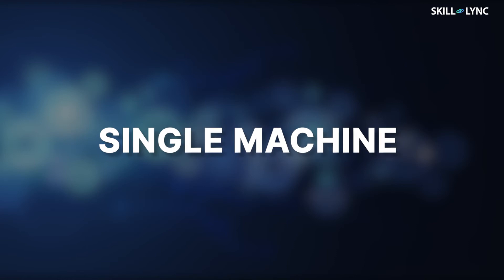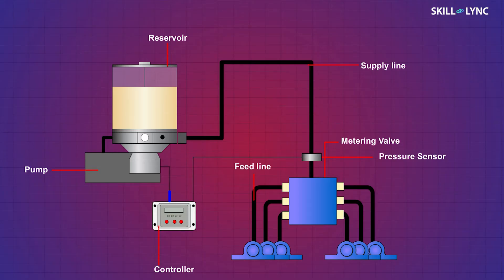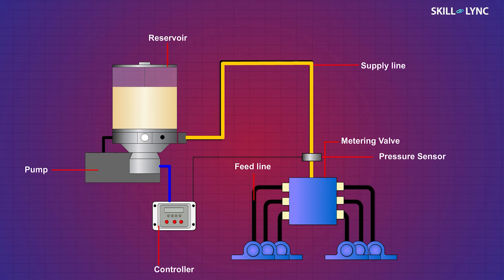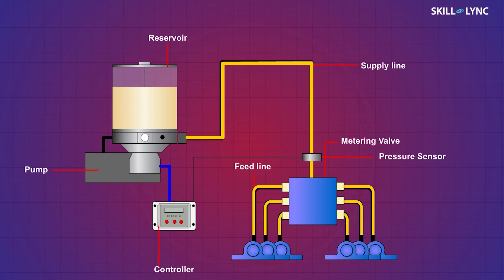When the controller sends a signal to the pump, the pump pumps the lubricant from the reservoir to the metering valve through the supply line. When sufficient pressure is attained, the metering valve delivers the lubricant, which gets passed through the feed line for lubricating the surfaces. Once sufficient pressure is developed in the supply line, the controller shuts off the pump.